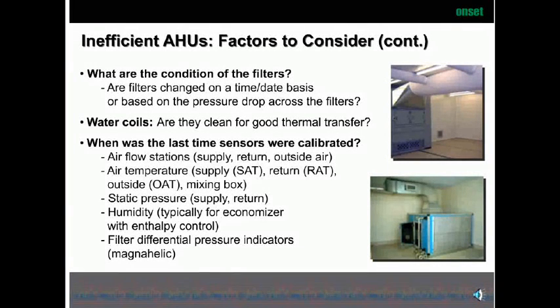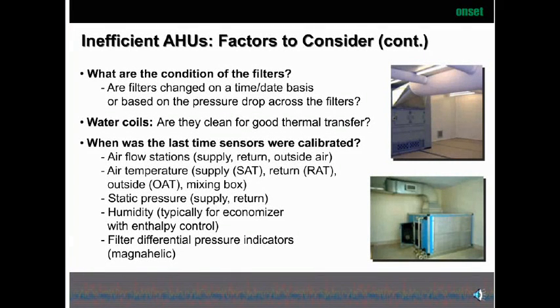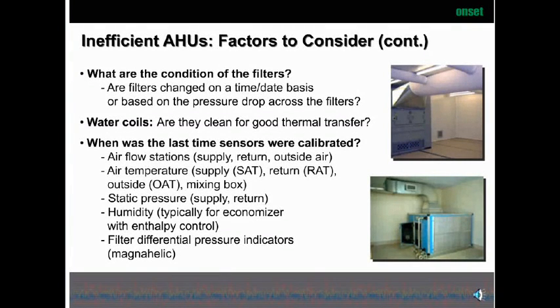Some other factors to consider are the filters. We find filters are often neglected and changed only on a time basis. But what happens if there's construction in the area and the filters get contaminated and clogged? The system tries to make up for all that clogged filter and doesn't function as well. A better approach is to look at the pressure drop across those filters and monitor it. Water coils — are they clean? Have they been power cleaned? Have you taken care of those coils so you get good thermal transfer? That is neglected quite a bit as well.